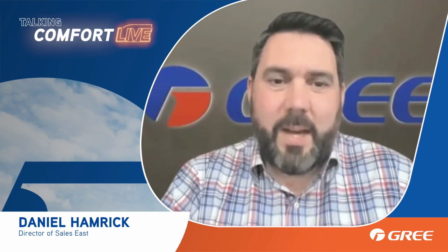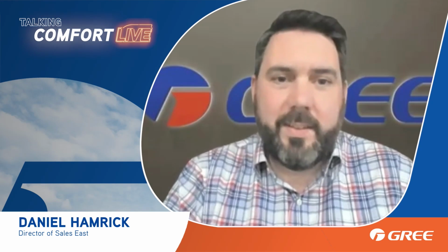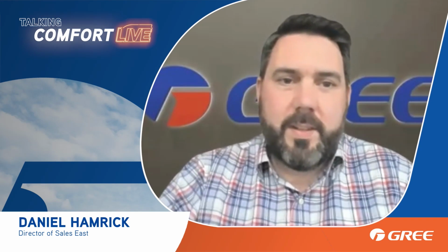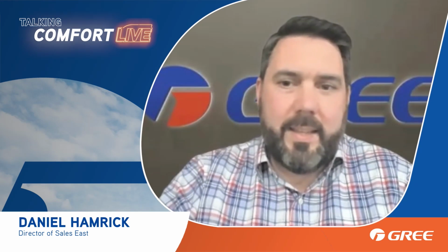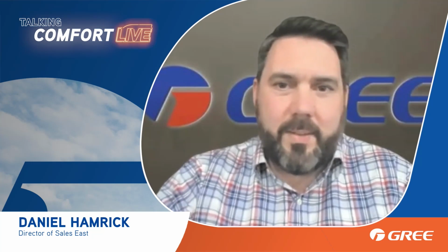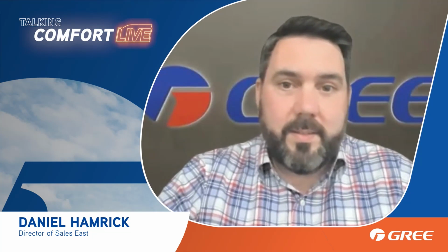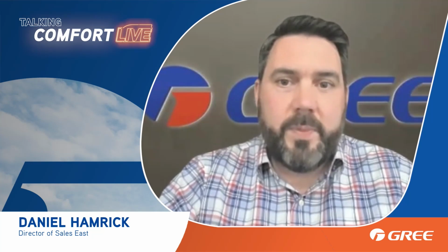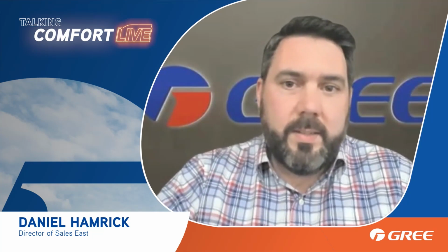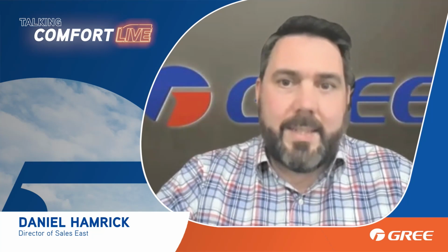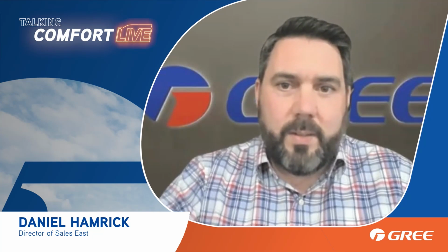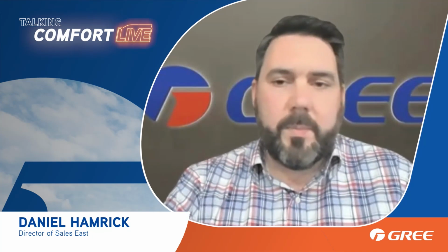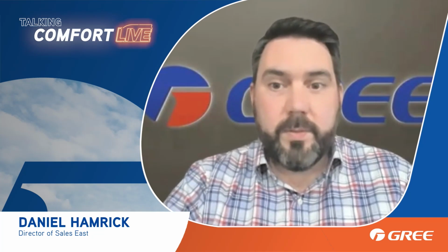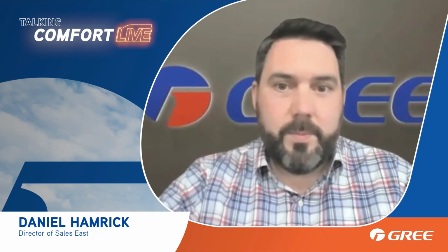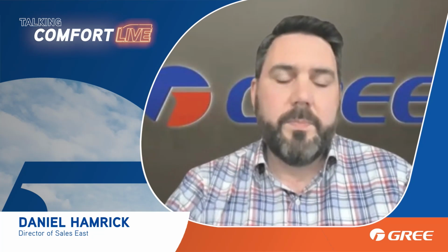What were you going to say, Dan? I was just looking at the extended rating on the Vireo, for instance. You got a 9K that puts out a little over 7,000 at negative 22. Then you go up to the 2-ton, and it puts out around 19,000 at negative 22. Those numbers are actual, so that's what we need to look at.